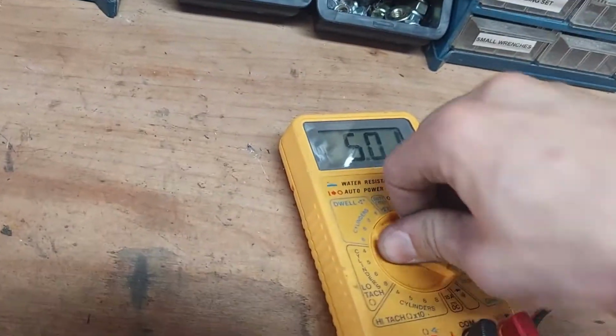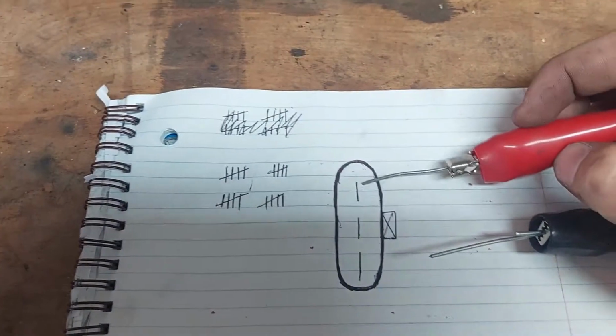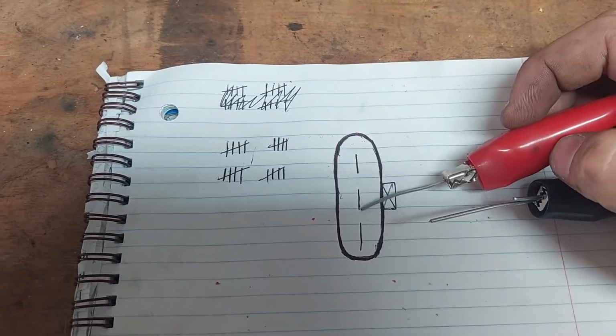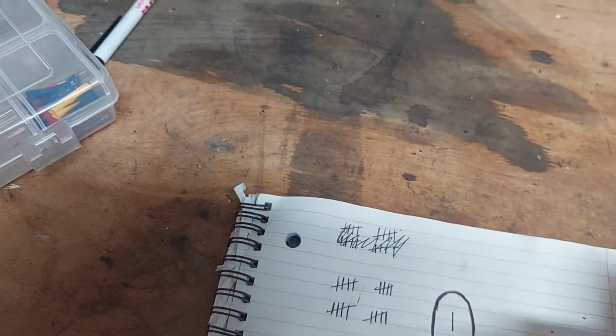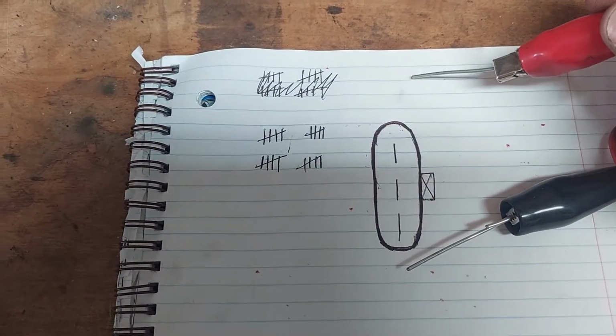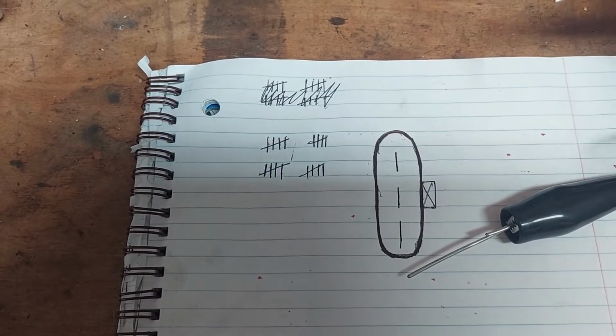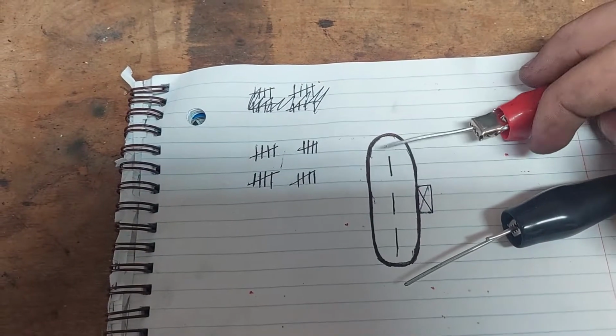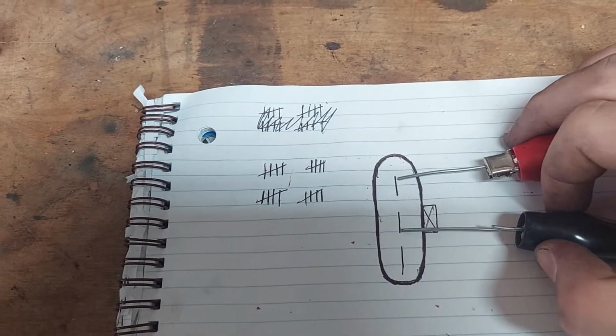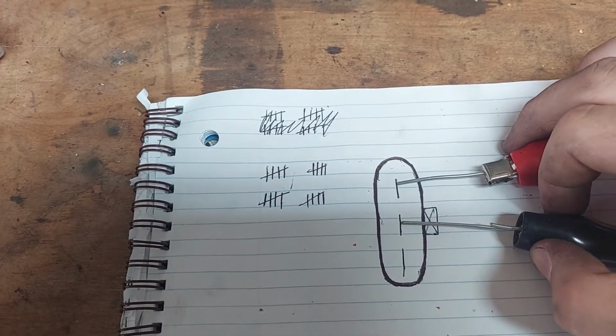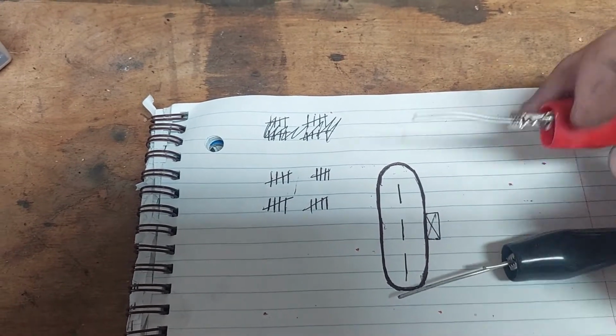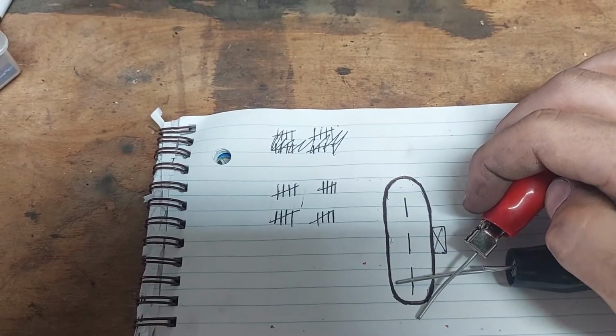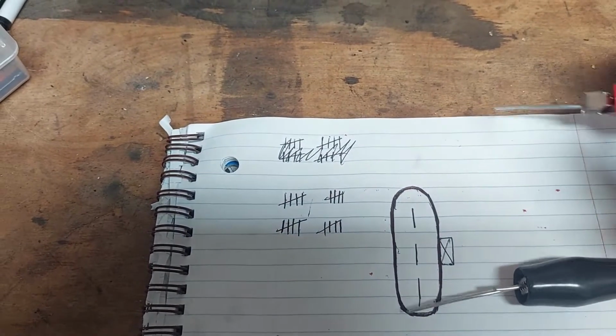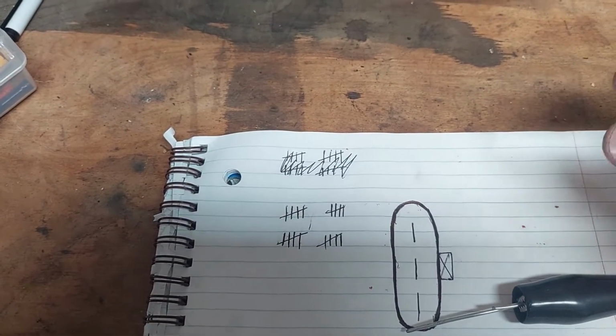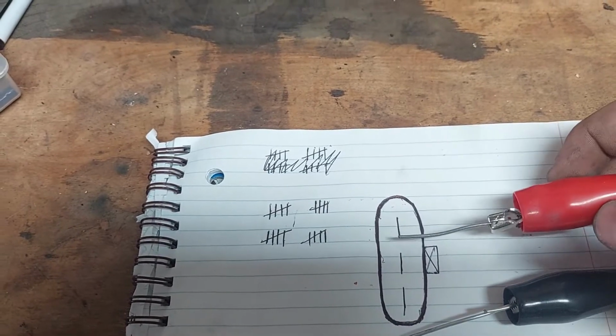Set the multimeter to continuity mode and test continuity between this pin and this pin. With the 0.015 feeler gauge in there, there should not be continuity between these two pins. When you touch these two pins together, if it makes a beeping noise, it shouldn't—at 0.015 of a space, it should not be making continuity.